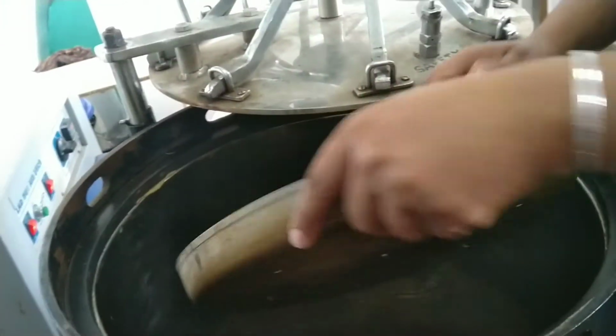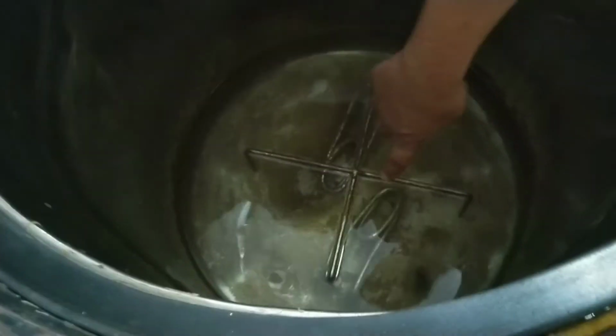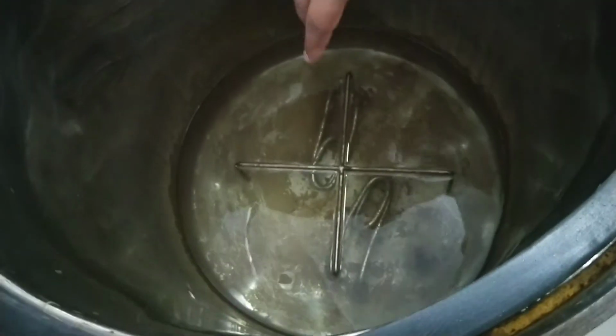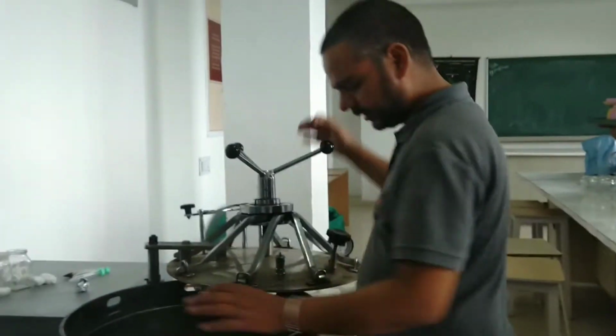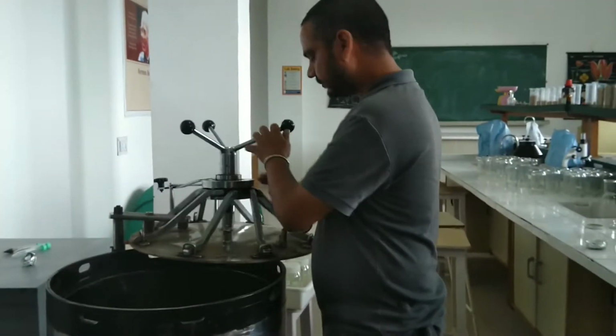This is the tray to place the glassware, and this is a stand to place the tray, and these are the heating rods. Autoclave has one or two heating coils, and the water level should be such that the heating rods are completely immersed in the water, and it is just close to the level of the tray.